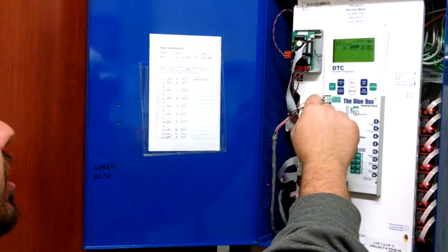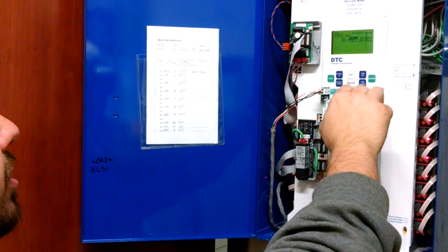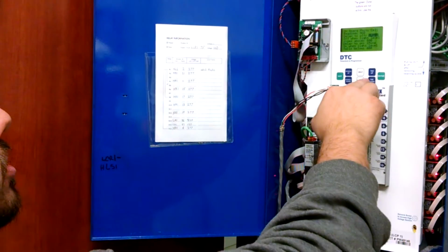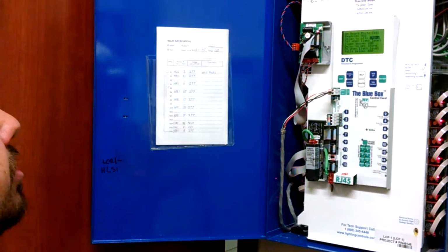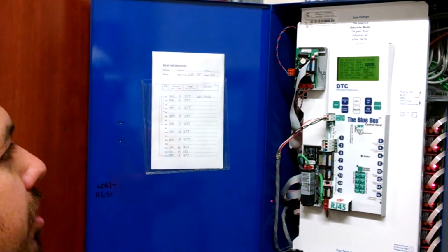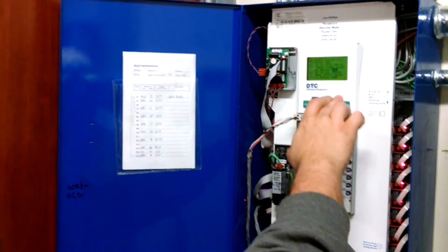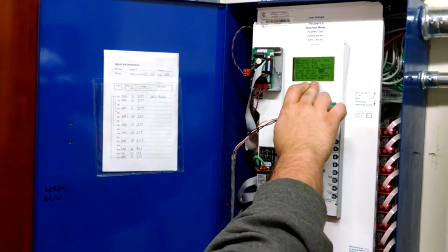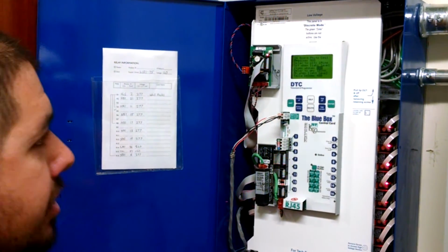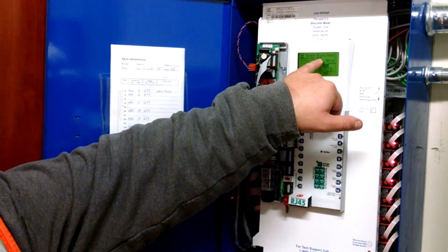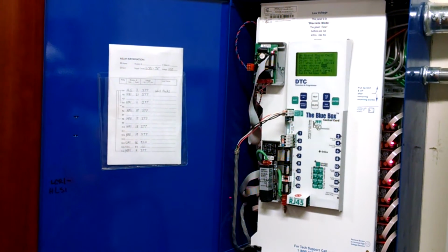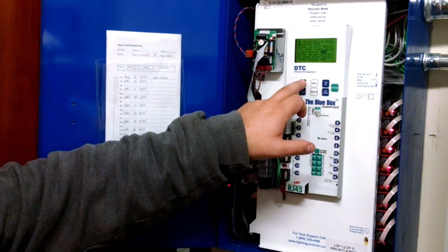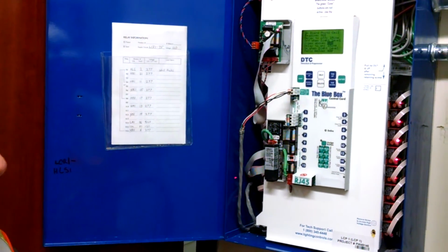Okay. If we need to adjust the sensitivity of this photocell, we can highlight photocell, press enter. And here are the set points. There are 1 minute delays for when the lights turn on and off. And if you look here, off when light level rises above 600, on when it falls below 400. Since our current reading with a good day of sunlight is 988, those settings should work pretty well, but if they need to be adjusted, you can just highlight them and press scroll up or scroll down to adjust. Okay.